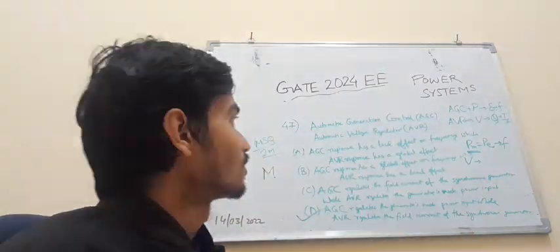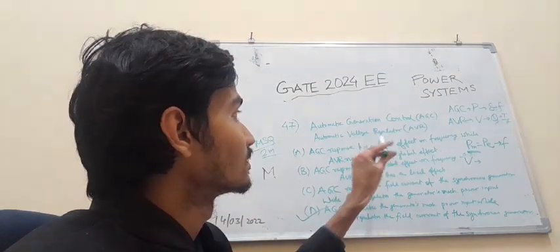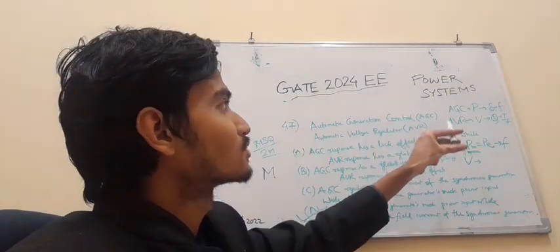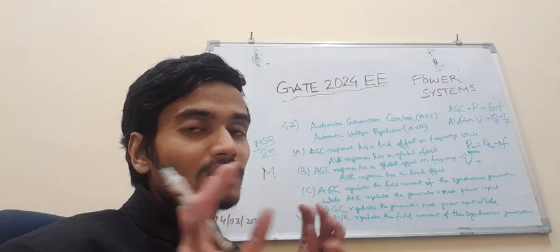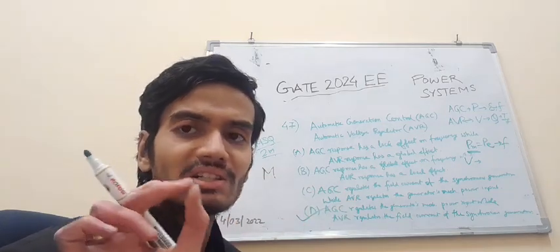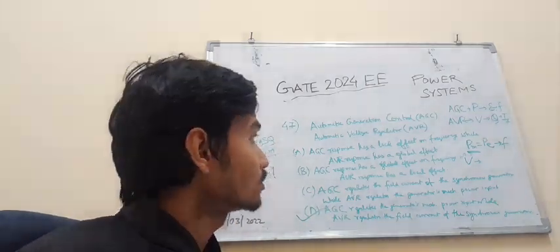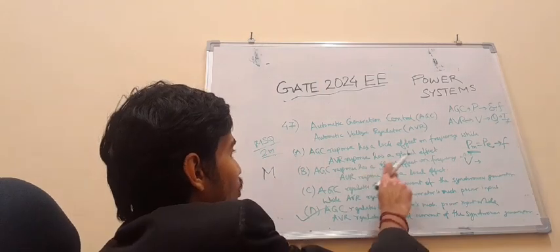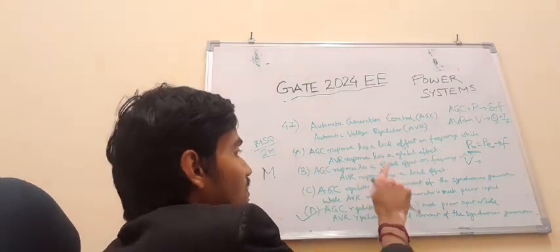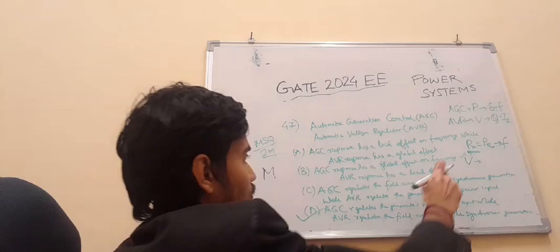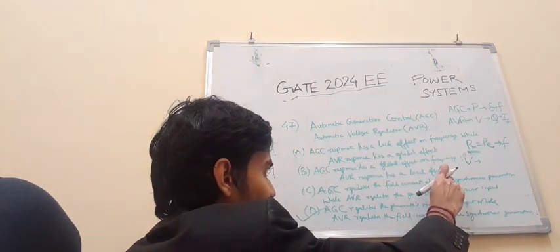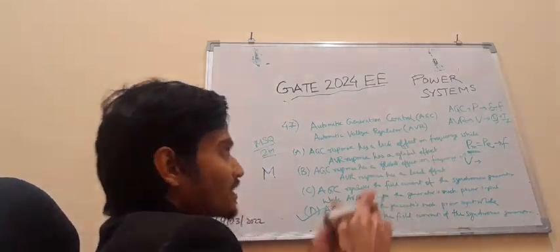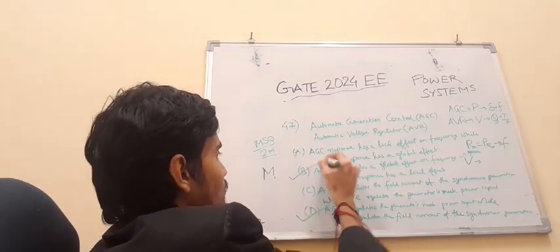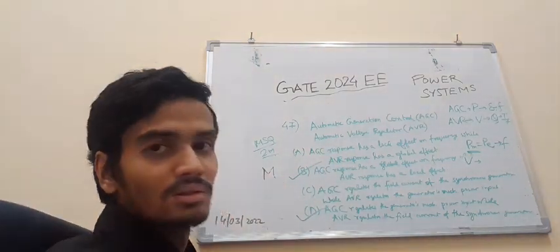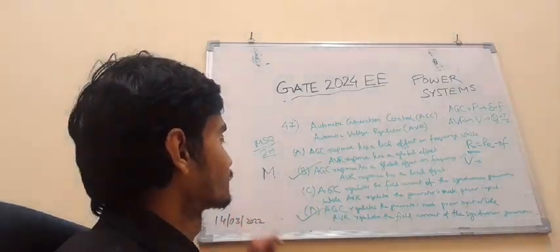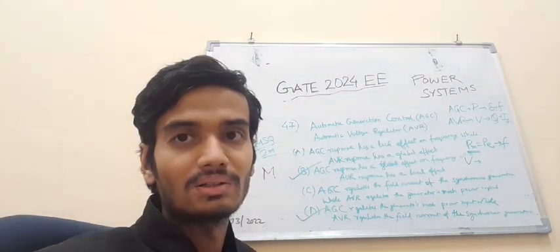While AVR will have a local effect, because voltage control will be restricted to the excitation system of that particular generator. So AGC response has a global effect on frequency and AVR response is a local effect, on a particular generator's excitation system, whereas AGC has a global effect on the frequency of the entire power system. So it is B. So the correct options for this question are B and D, as I have discussed.